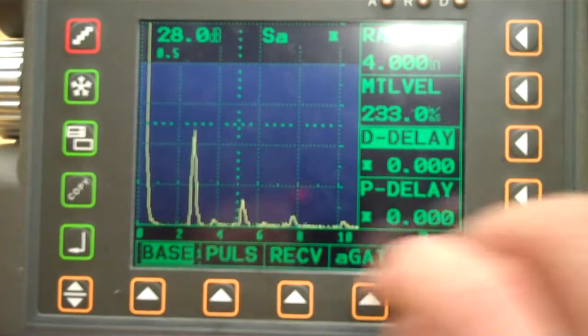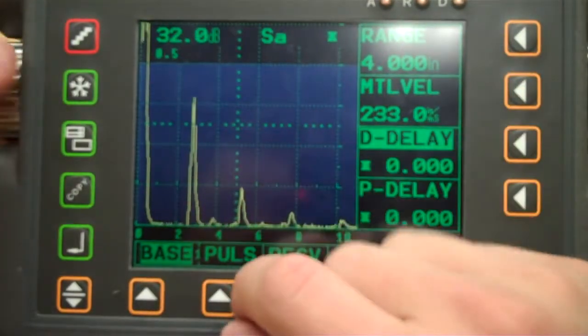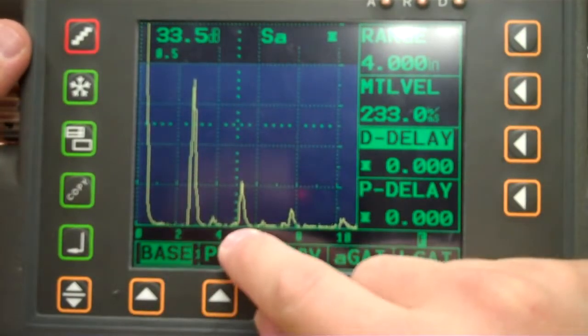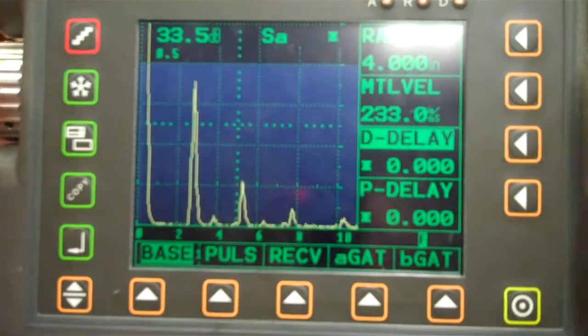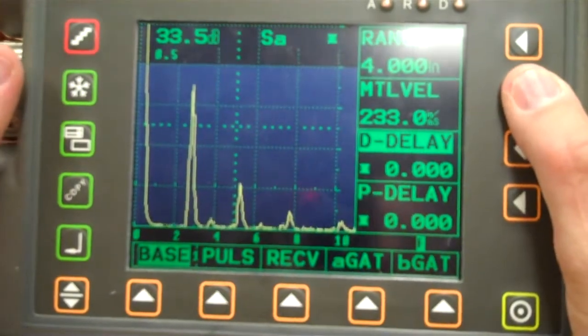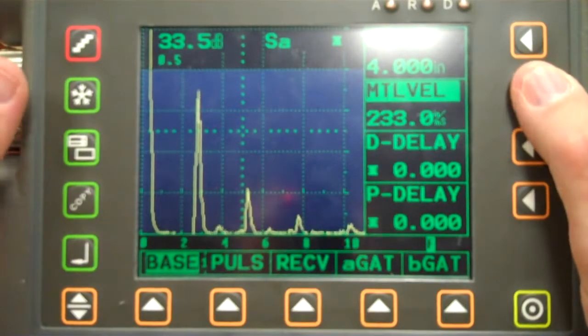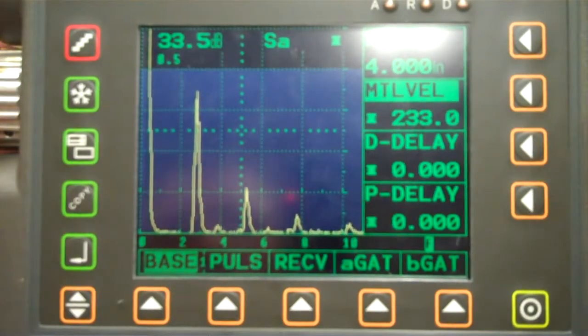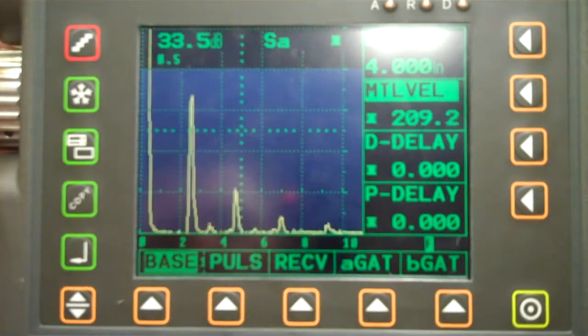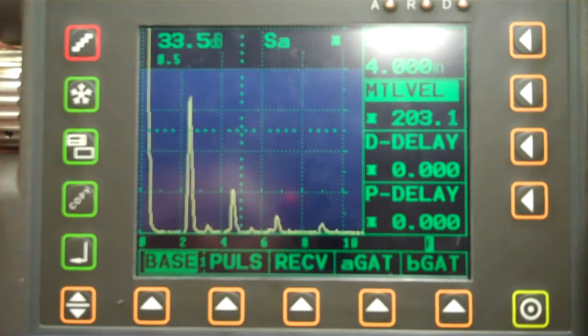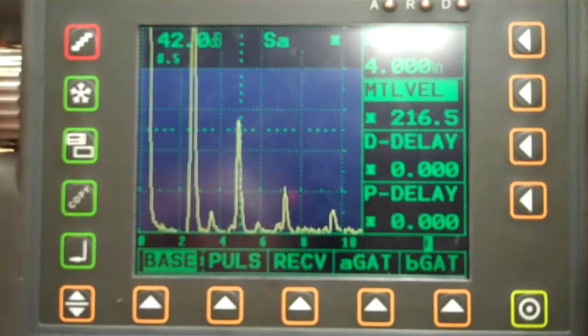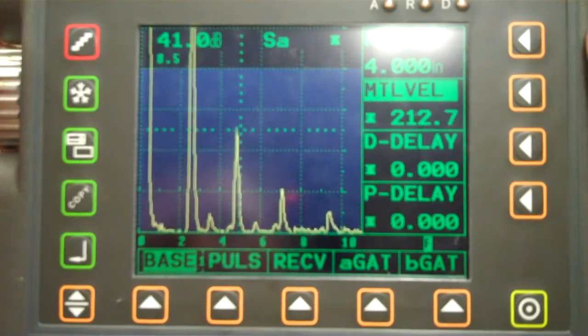So there. Now we're close. We're 20. Let's give it some gain here. We're pretty close to 25. We're a little past 50. We're past 75. We're past 100. So we're going to do that with the fine range or material velocity. Okay, I'm going to just move that a little bit at a time here. I'm just bringing that in, and you see this back signal over here moving in. If I just keep going, I'm going to keep pushing it in, but I don't want that. So I want 1 inch, 2 inch, 3 inches, 4 inches. Give it some more gain just so we can see what's going on here. Okay, I'm going to roll that back. Whoops, wrong way.